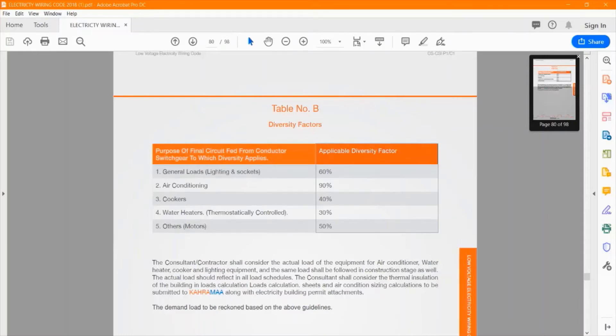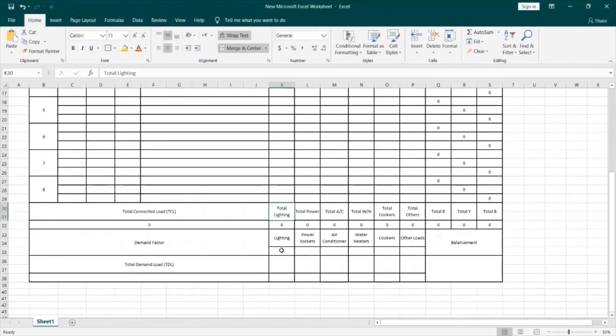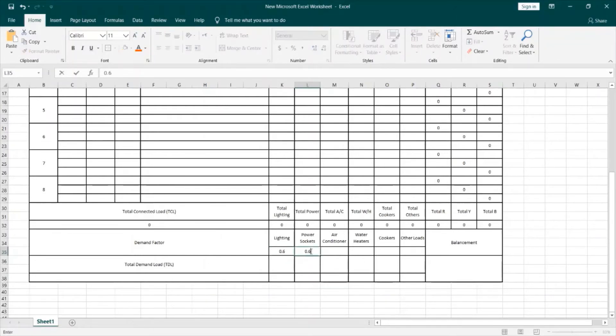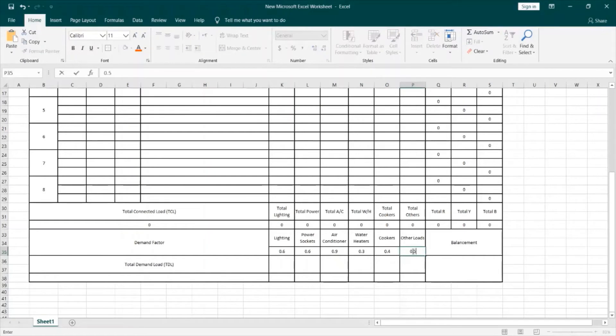Let's get back to our schedule. Now, I will define the demand factor for lighting as 0.6, as we have seen. For sockets, also 0.6. Air conditioner will be 0.9. Water heaters will be 0.3, cookers 0.4, and other loads 0.5.